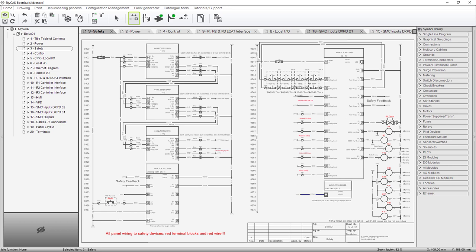So we added additional e-stops. We added the air dump. This is a valve that in order to be open has 24 volts on it. So it's a safety output so to speak. And if you hit an e-stop then it will kill this. This dump valve will dump all the air off of the machine actuators into the atmosphere. And then once you power it back up the valve closes in the dump side and opens in the pass through. So plant air can go through to the SMC valve manifold. We may have had the reset button in here before. I can't remember. But this is the reset button to reset the whole safety system. It is on the HMI pendant. So I think that's all that's changed on this print.